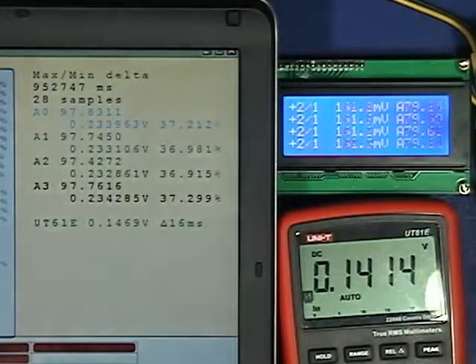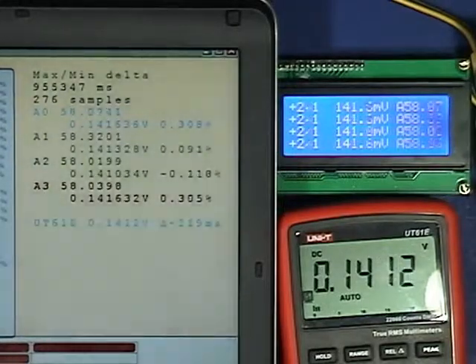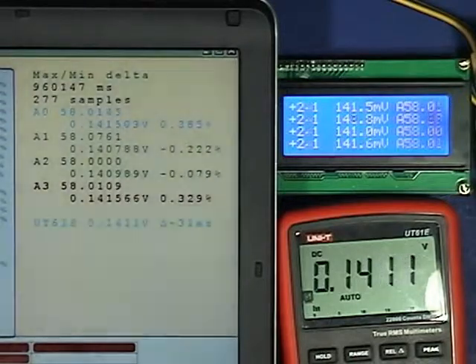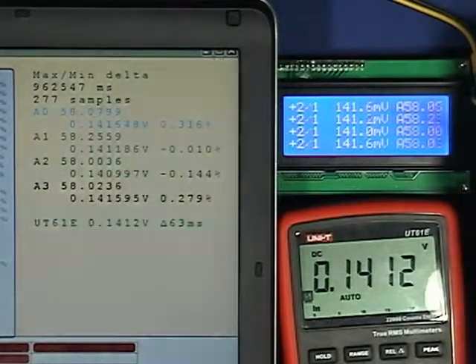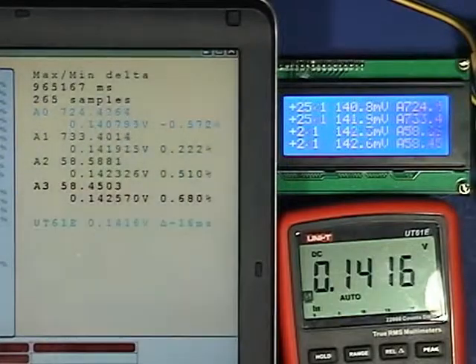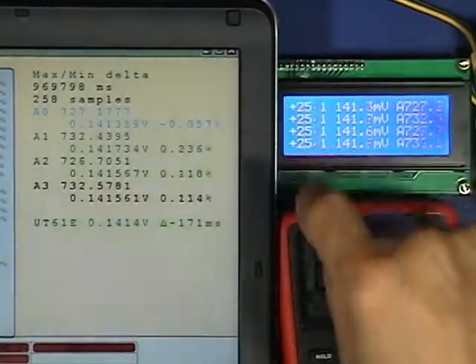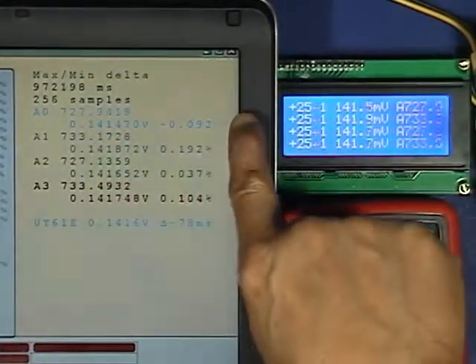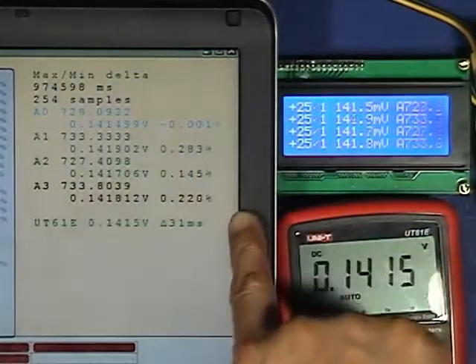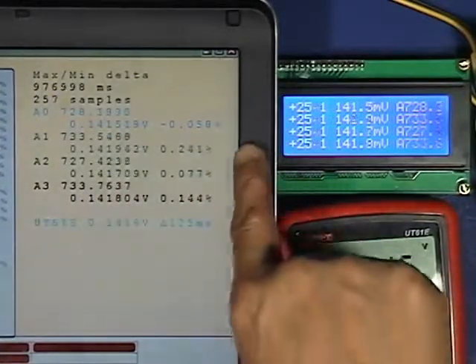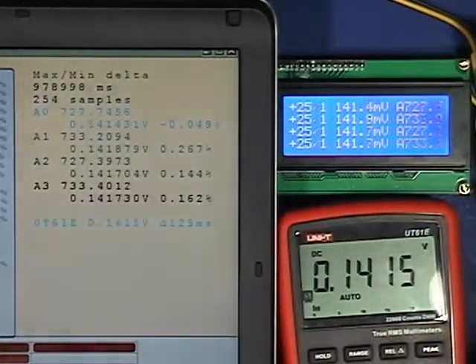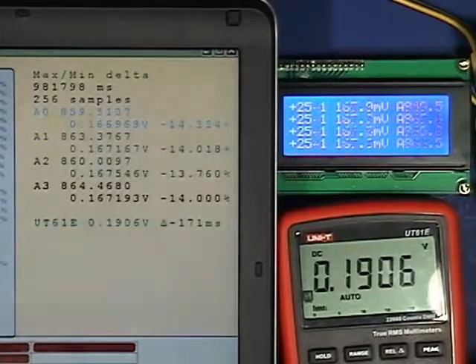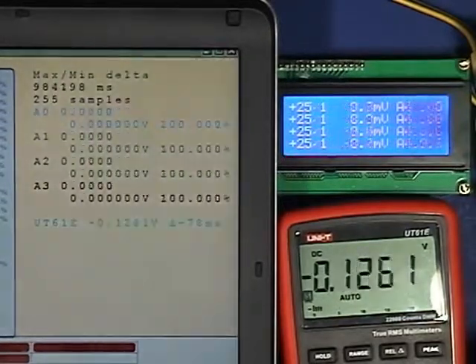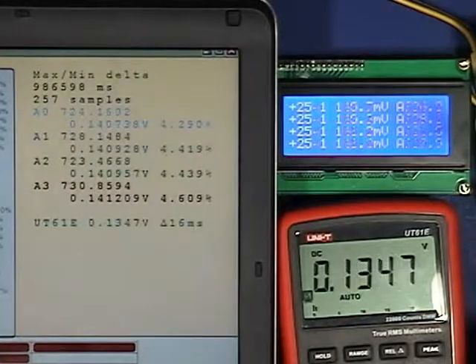Now we're into the real difficult area when the voltage is this low. Right now we're talking 140 millivolt. I'm going to switch to the most sensitive range and see how it measures. There's the 25 multiplied by 25. Very respectable error rate, less than 0.3% error. Next stopping point should be around 60-70. That's where I expect some changes.